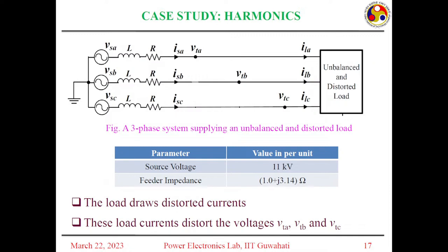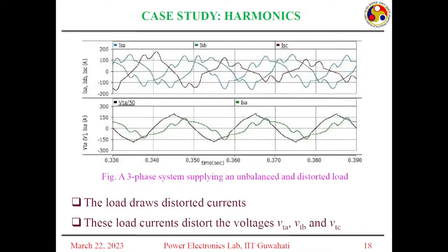But what happens is, since ILA is distorted, what is the voltage VTA here? VTA is VSA minus ISA times the feeder impedance. ISA has harmonics. Because of these harmonics, VTA, the voltage at the load, will also be polluted. So we will see the simulation here.